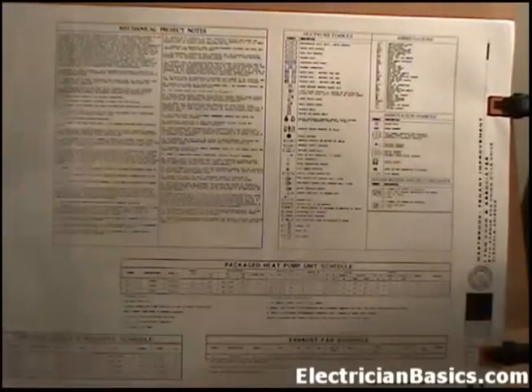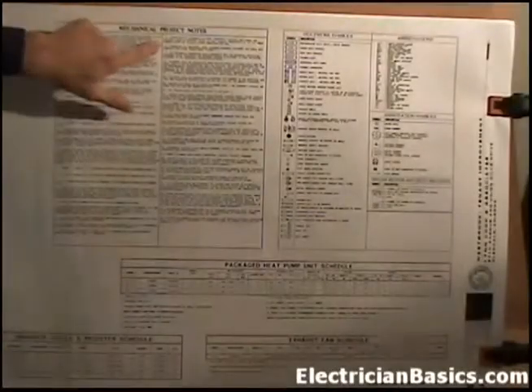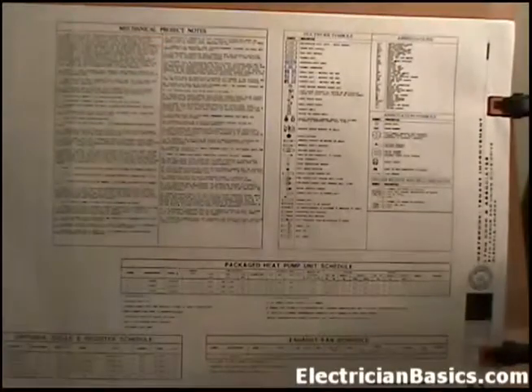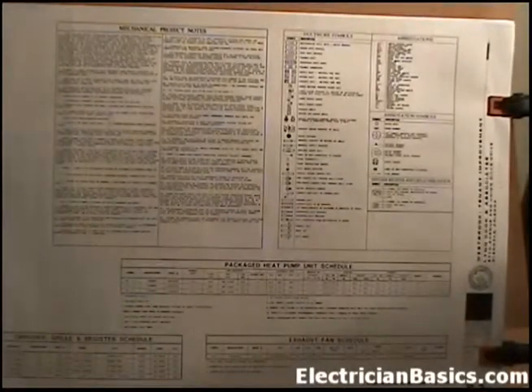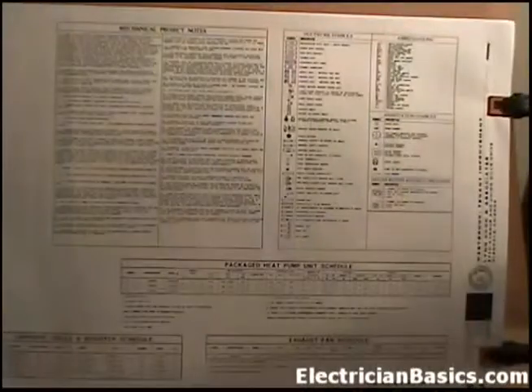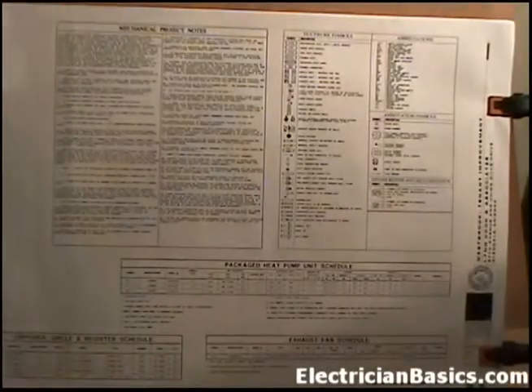Basically, we've got some mechanical project notes up here. Most of these notes refer to the mechanical equipment, but some things directly affect our electrical work. Look at note W: contractor to coordinate all final thermostat locations with owner and architect prior to mounting. Mount all wall-mounted thermostats at 48 to 54 inches above finished floor for disabled access compliance per UMC. Since you'll be installing the boxes for these thermostats as an electrician, you need to know that dimension, 48 to 54 inches above the finished floor.